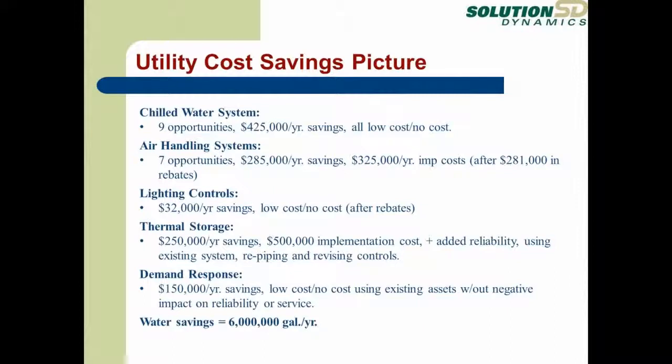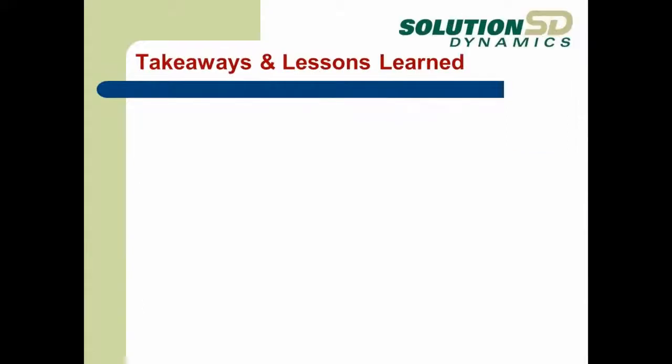In addition, all this electricity that gets saved ultimately gets dumped out of the cooling tower. So the electric savings translate into less load out the cooling tower, and less load out of the cooling tower means less water that's evaporated. So there's also the opportunity to save a significant amount of water with all of it. And this moves their PUE from what is actually around 1.5 to closer to 1.35.